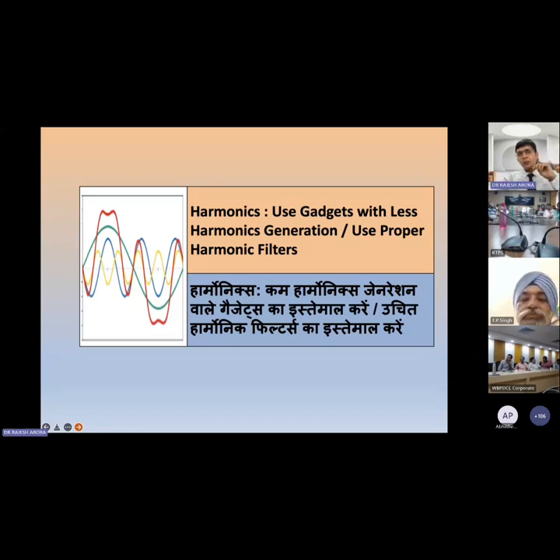These are detrimental to your wiring system and distribution transformer. They generate more heat in the neutral. If you haven't chosen the proper size of neutral, because of harmonics, which is the most ignored subject, fire will take place. And at the end of the day, you will be totally clueless about what happened. And again, the report will say the fire broke out because of a short circuit. Time to wake up.